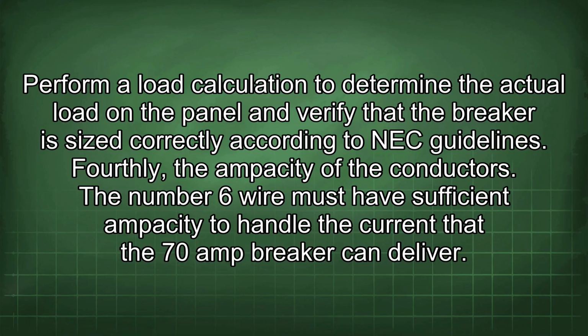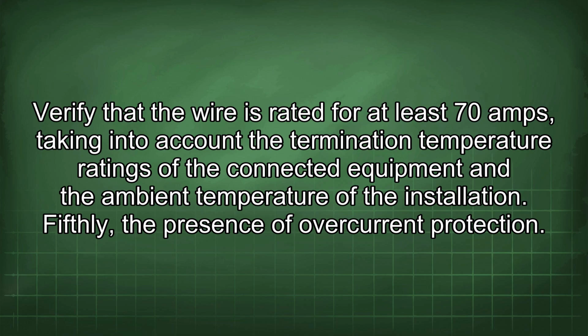Fourthly, the ampacity of the conductors. The number 6 wire must have sufficient ampacity to handle the current that the 70-amp breaker can deliver. Verify that the wire is rated for at least 70 amps, taking into account the termination temperature ratings of the connected equipment and the ambient temperature of the installation.